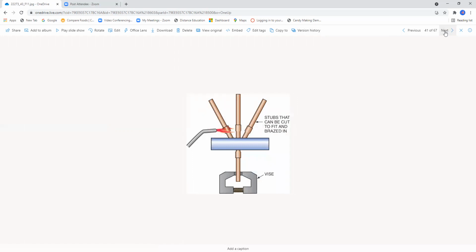It shows the removal, heating up. In fact, you'll find this on page 1279 of your textbook under figure 43.11. The valve and stubs are being held in a vise while additional stubs are being brazed in. Remember, the valve body must be kept cool during the process. The valve and stubs can be removed from the unit by cutting the stubs off. They recommend, in this case, that you braze on stubs prior to installing a replacement reversing valve.